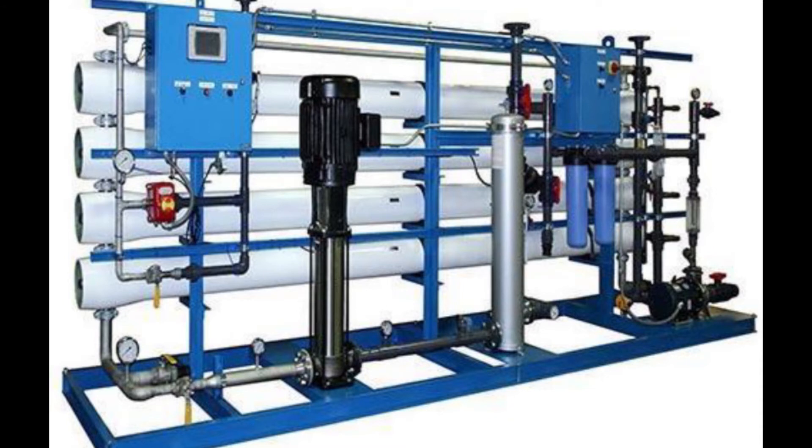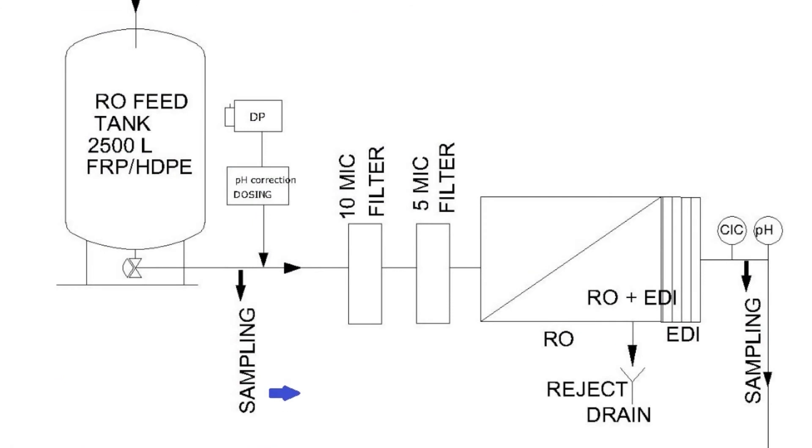Within the membrane system, the feed water will be split into pure water called the permeate and a high concentration of solute water called the reject. RO is capable of removing dissolved salts, particles, colloids, organics, bacteria, and pyrogens from the water. The membranes do not remove any gases.